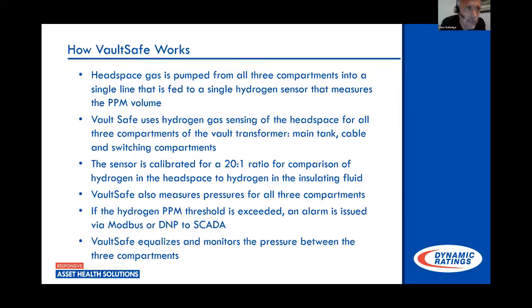And that turned out to be a great thing. The first one I installed actually found a huge leak in the top of the cable compartment that the company did not know they had. And this was kind of their test plot. They had pressure transducers on all these compartments. But if you have a cable compartment that's not pressurized, zero pressure in a sealed compartment is no different from zero in a compartment that's open to completely open atmosphere. It could have a huge hole in the top of it, and they both look the same when you're looking at pressure.